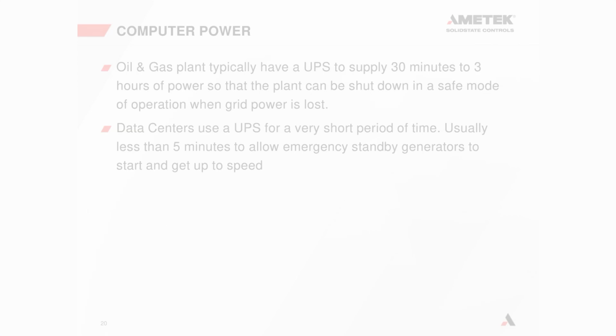So the UPS at a data center is only there to cover the period between the first loss of power and the time that the emergency standby generators get up to speed and can be put online. It's not for a prolonged period of time. It's only for that short period between loss of power and generator up to speed.